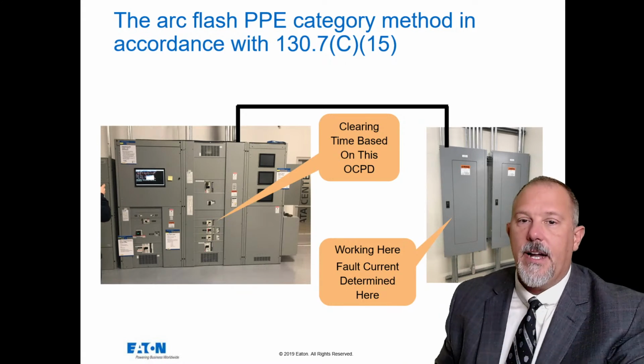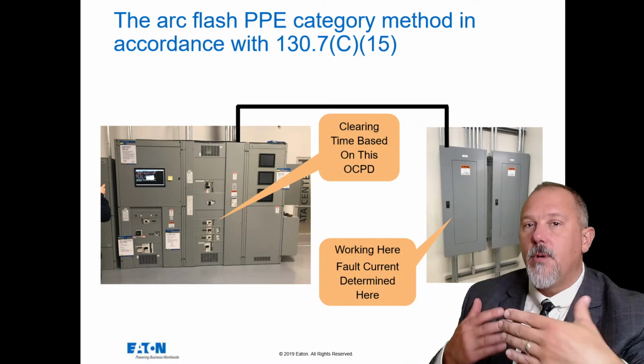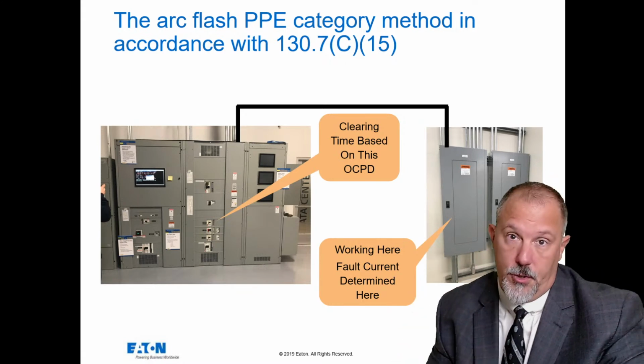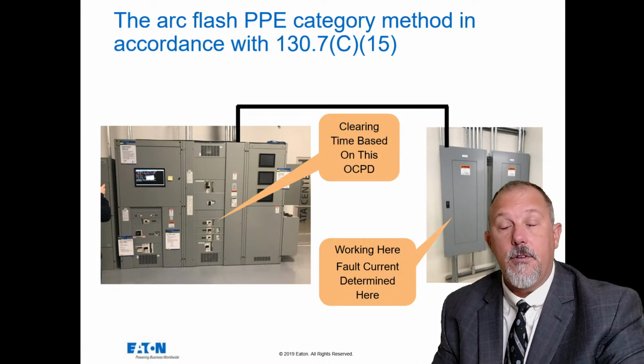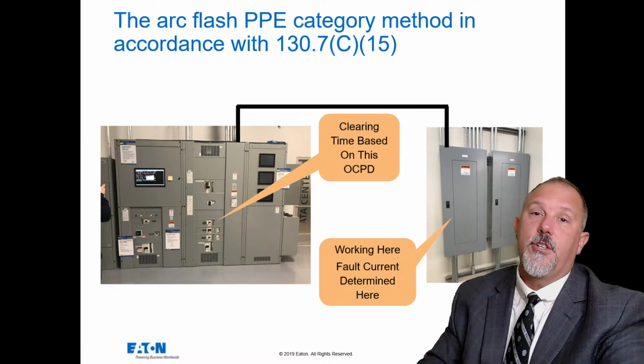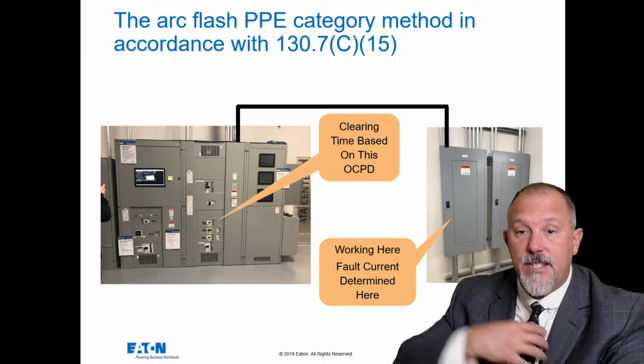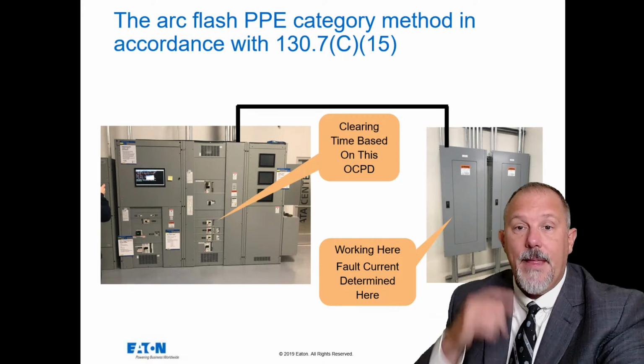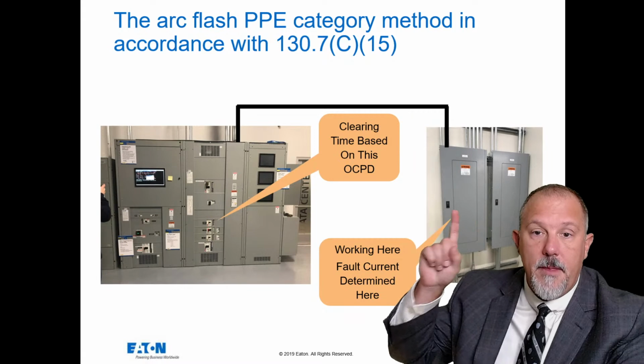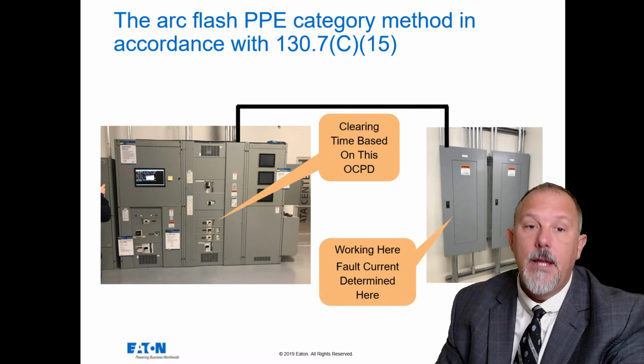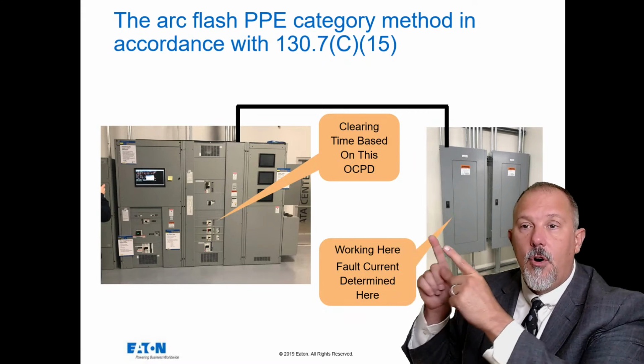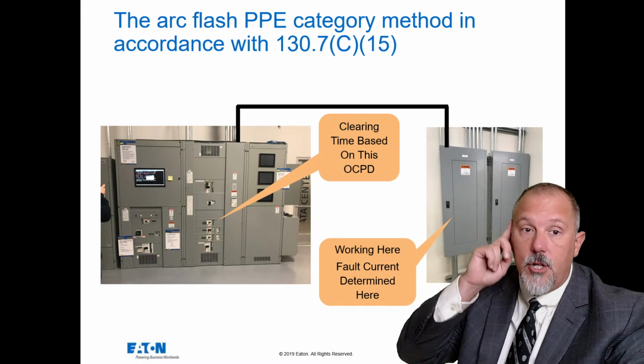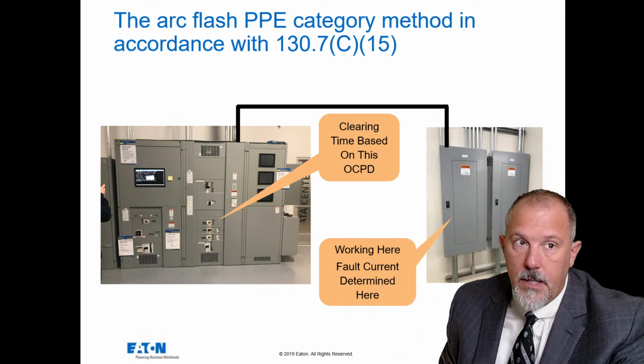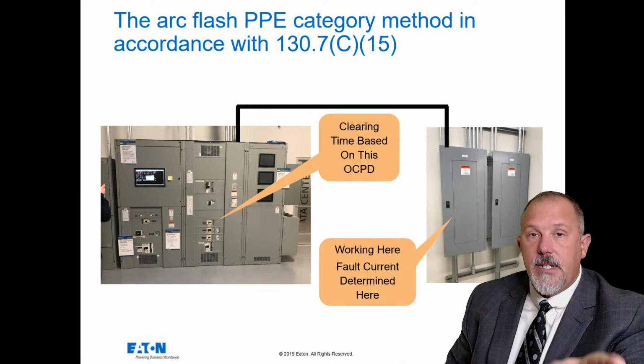When it's justified, I take that panel cover off. Say I'm troubleshooting, a good example of justified energized work, and I need to take voltage measurements. I'm going to need to dress for the energy. And that energy in this panel is not based upon the main overcurrent device in that panel. It's based upon the overcurrent device feeding the panel. So let's say, for example, it's a 30 cycle delay.